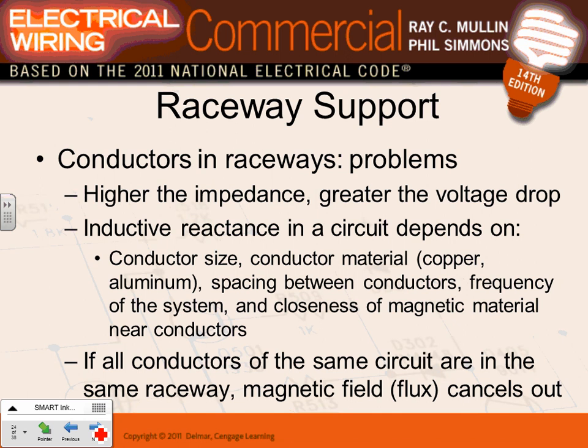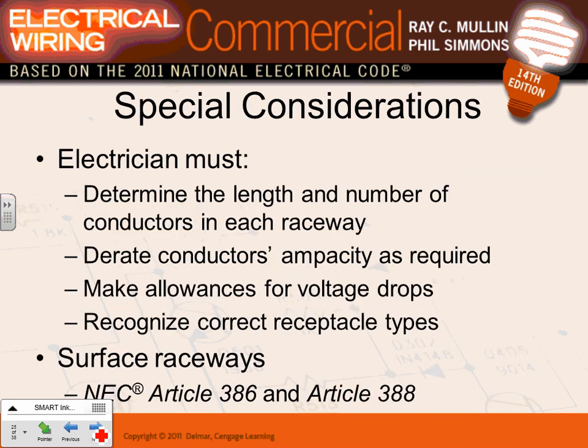All conductors of the same circuit must be installed in the same raceway because it reduces inductive reactance and also reduces voltage drop. When all conductors are in the same raceway, the magnetic fields cancel. So phase A, B, C, neutral, and ground - all go inside the same conduit.